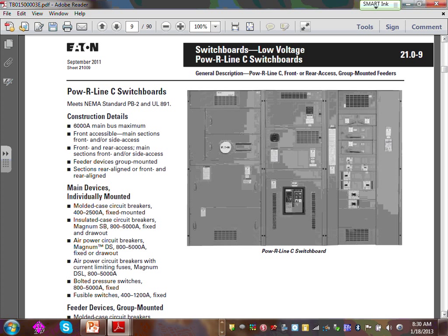Can you guys see the amps that you can get these boys at right here? Anybody can get the amps from 800 amp all the way to what? 5,000 amp. Can I have thumbs up, Chad? We fully understand what a switchgear is. Now, typically if you need an 800 amp, it would be cheaper, Jeff, to do what? Panel board, right? Typically, it starts making sense if you go higher than 1200 amp. It starts making sense. Switchboard.